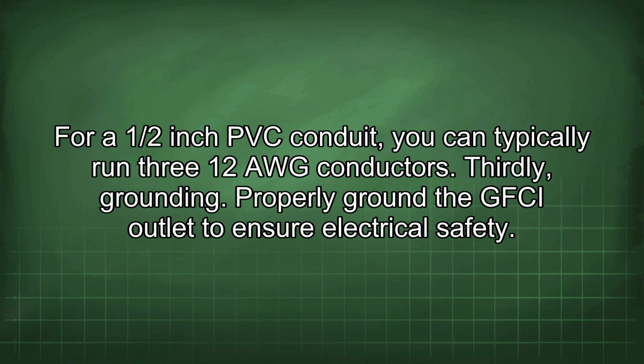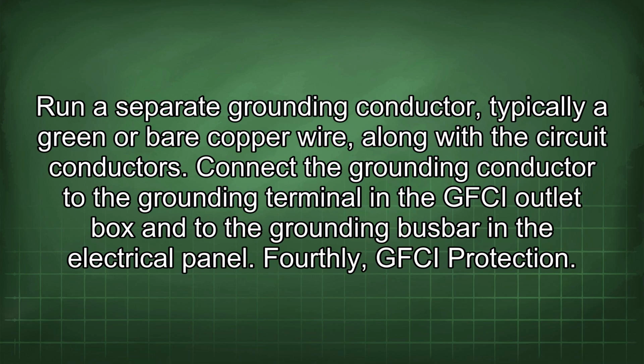Thirdly, grounding. Properly ground the GFCI outlet to ensure electrical safety. Run a separate grounding conductor, typically a green or bare copper wire, along with the circuit conductors. Connect the grounding conductor to the grounding terminal in the GFCI outlet box and to the grounding busbar in the electrical panel. Fourthly, GFCI protection.